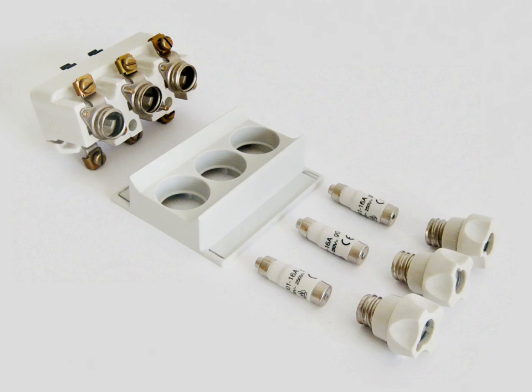See table. D0 type fuses are used for protection of circuits up to 500 volts AC in residential and commercial installations, and occasionally for the protection of electric motors. The most common operating class is gG, general purpose, formerly gL, but other classes are available. A gG class fuse will typically blow within 2 to 5 seconds at 5 times the rated current, and within 0.1 to 0.2 seconds at 10 times the rated current.